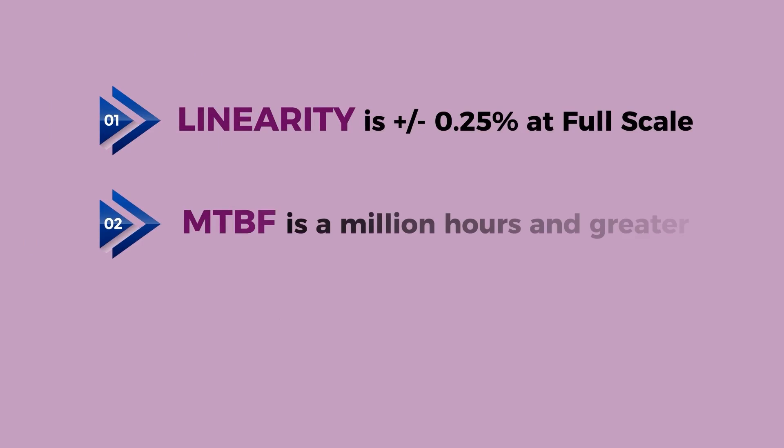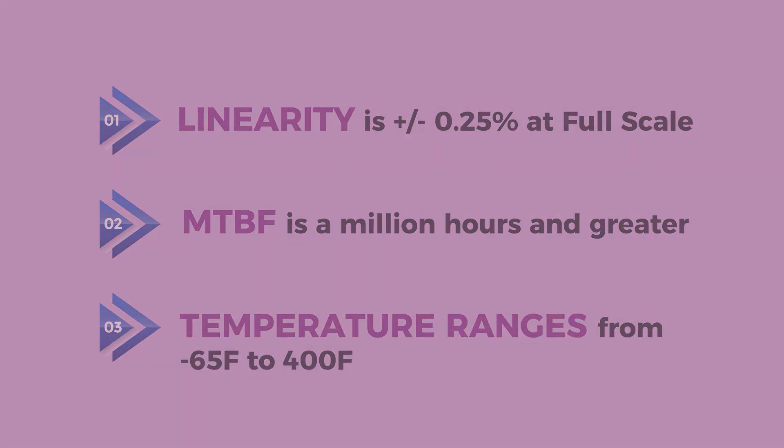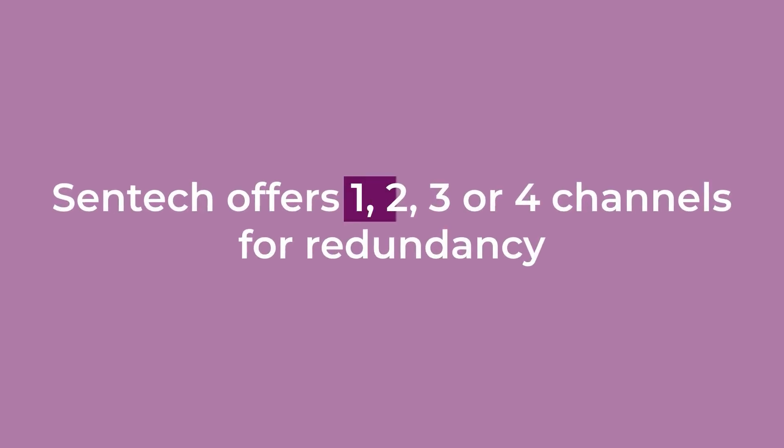Linearity is plus or minus 0.25 percent at full scale. MTBF is a million hours and greater. Temperature ranges from negative 65 to positive 400 degrees Fahrenheit. Sentech offers one, two, three, or four channels for redundancy, which can be either parallel or in tandem.